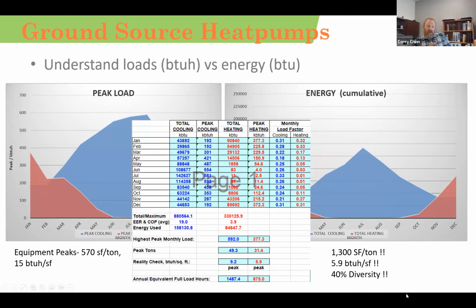Where people fall into a trap is if they look at, oh, I need only a 40 ton chiller for this 64,000 square foot building in order to compete with geothermal. That is not true. You actually need about a 90 ton chiller in order to properly cool this facility.